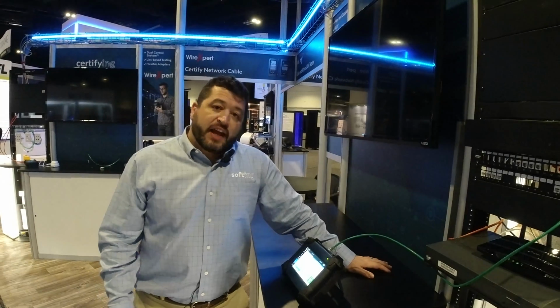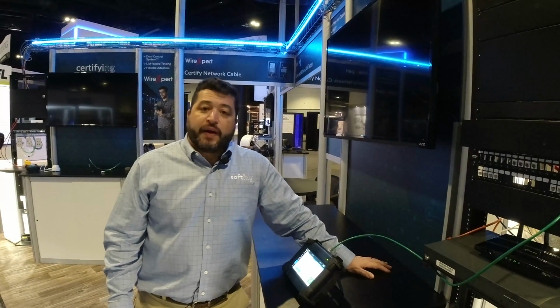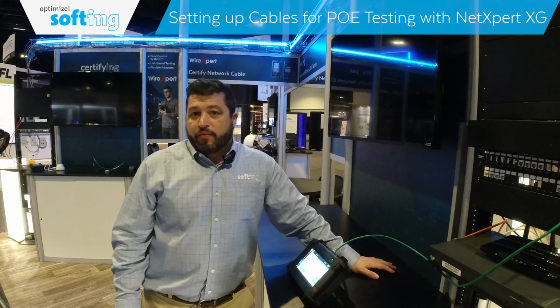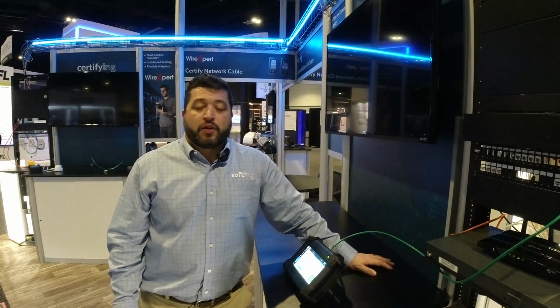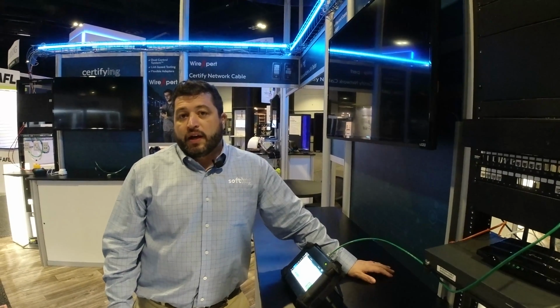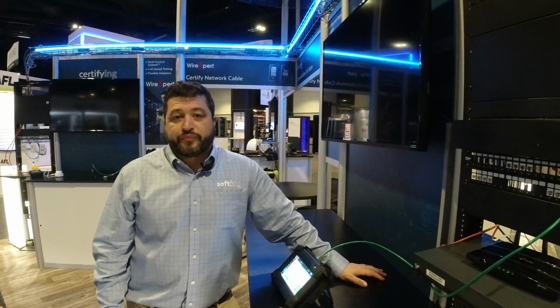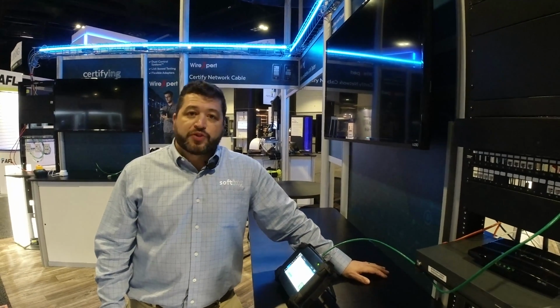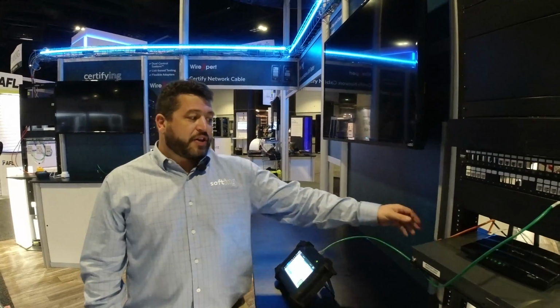Okay, so we've tested the cable that's going to be running to our camera, and it's passing for 1 gig. Now that camera at the end of this cable run is a POE camera. So let's bring in the patch cord from the POE switch and patch it in.